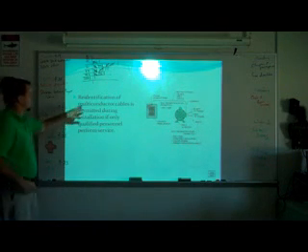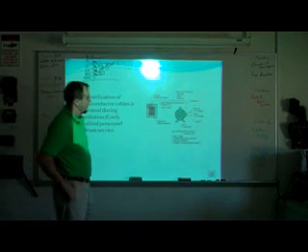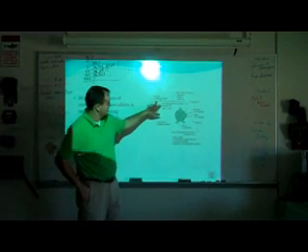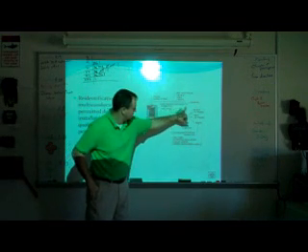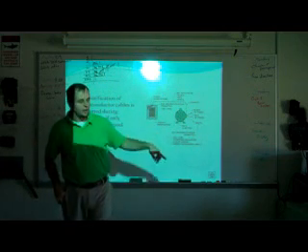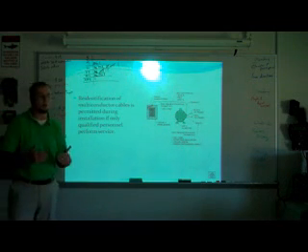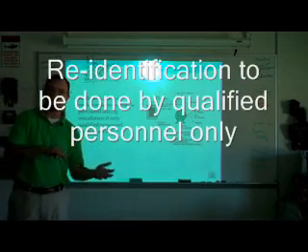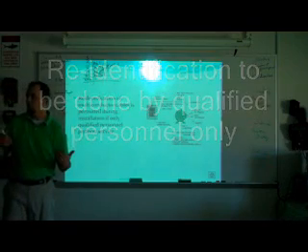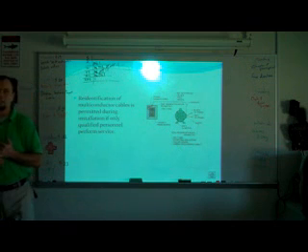Re-identification of multi-conductor cables is permitted during installation and only qualified personnel perform service. Okay. So here we're talking about two different conductors coming over here. Re-identification is where you use a white wire as a hot wire, right? That's where you're re-identifying. It's no longer a grounded conductor. Now it's a hot conductor with white covering. So it should be done only by qualified personnel.